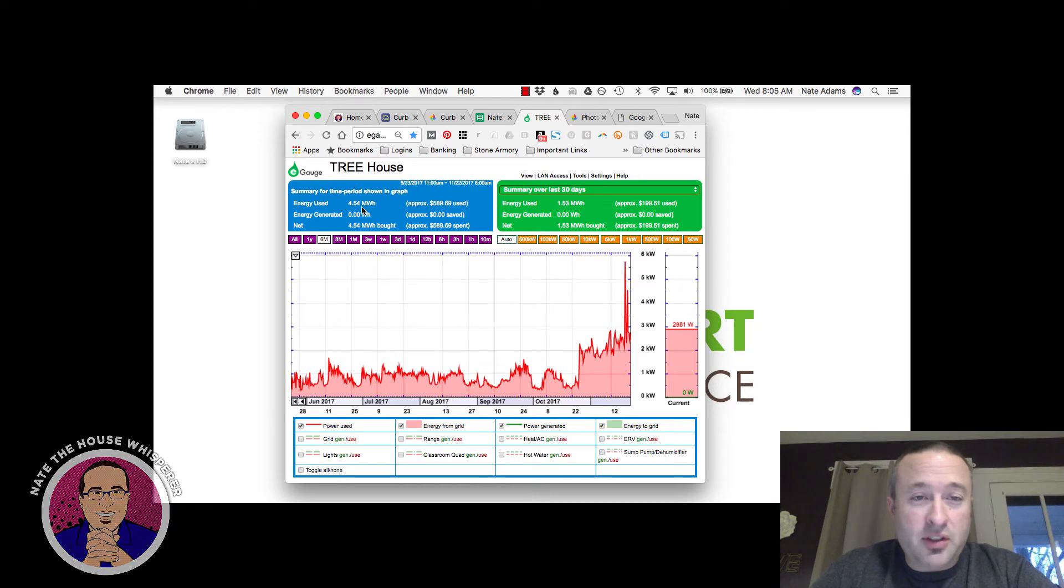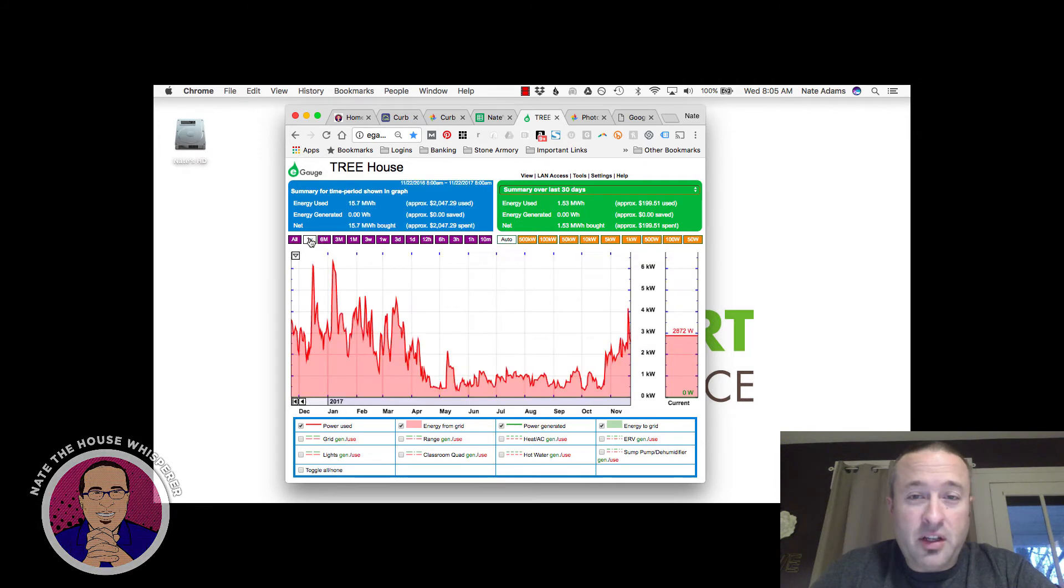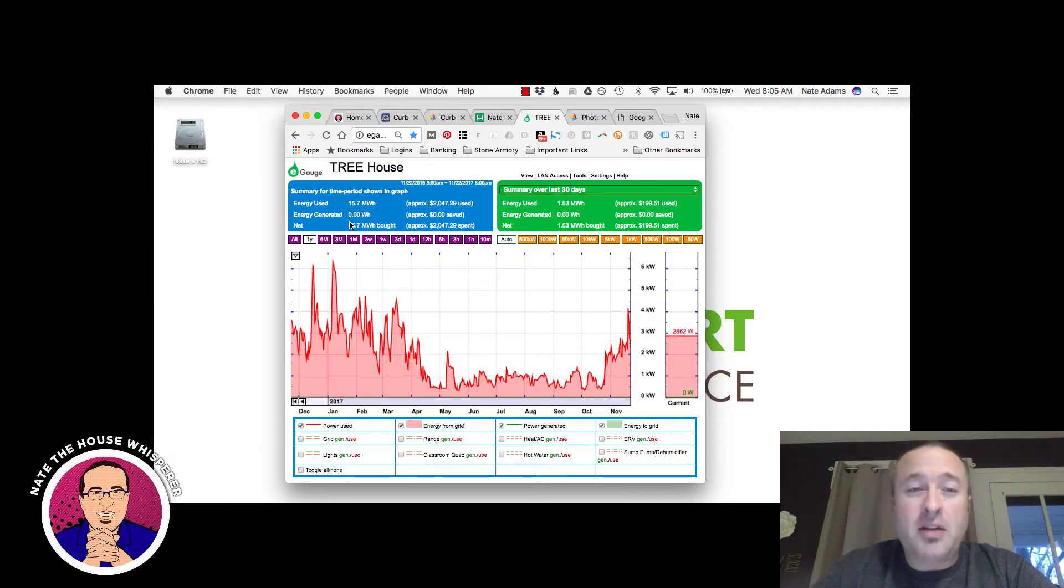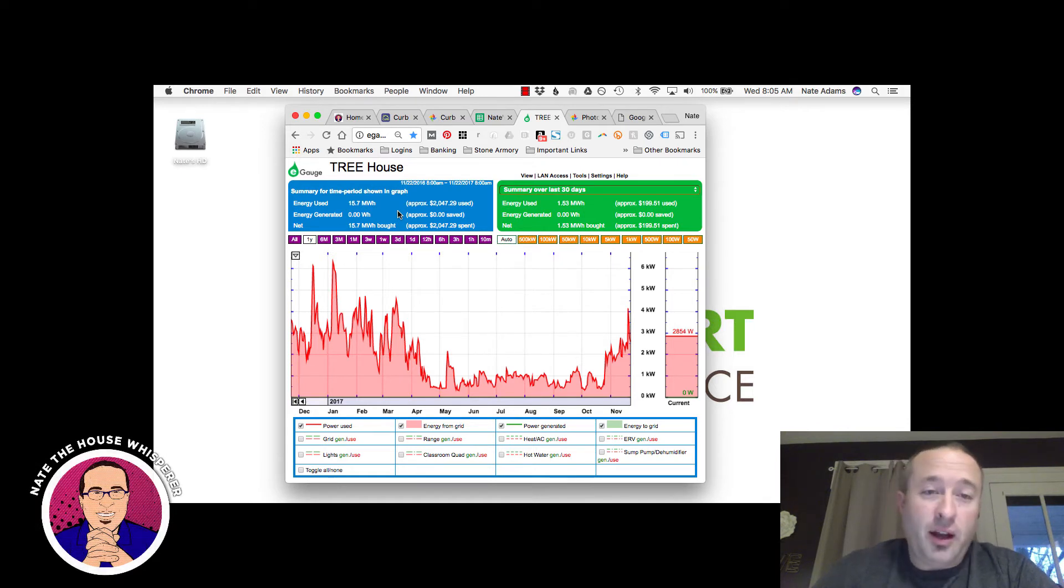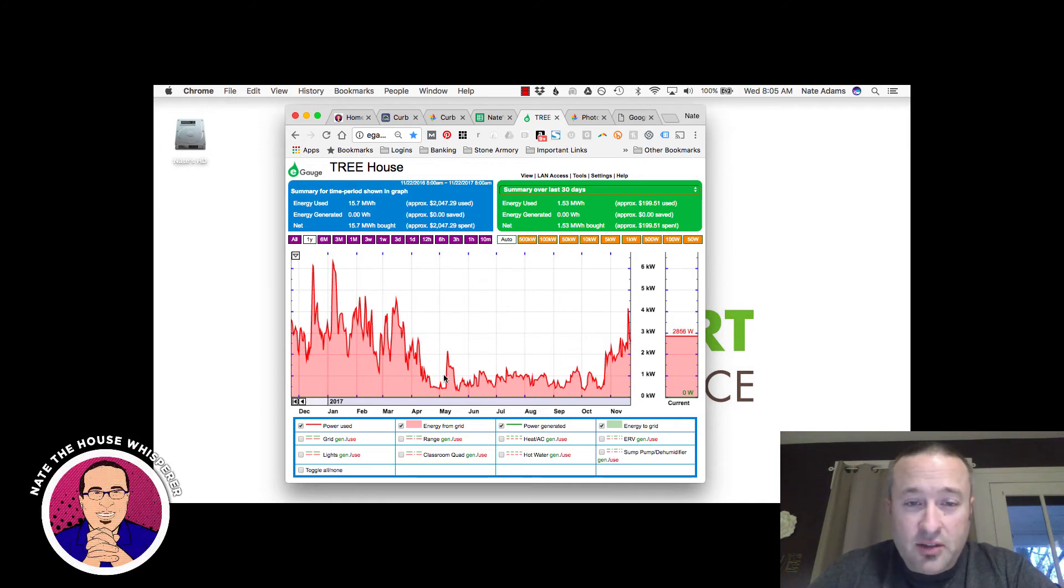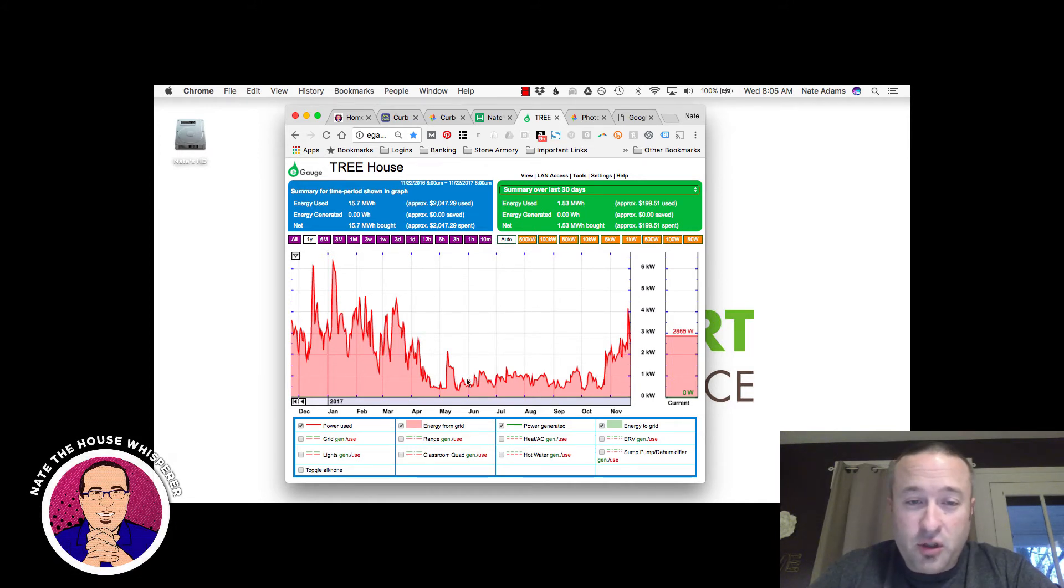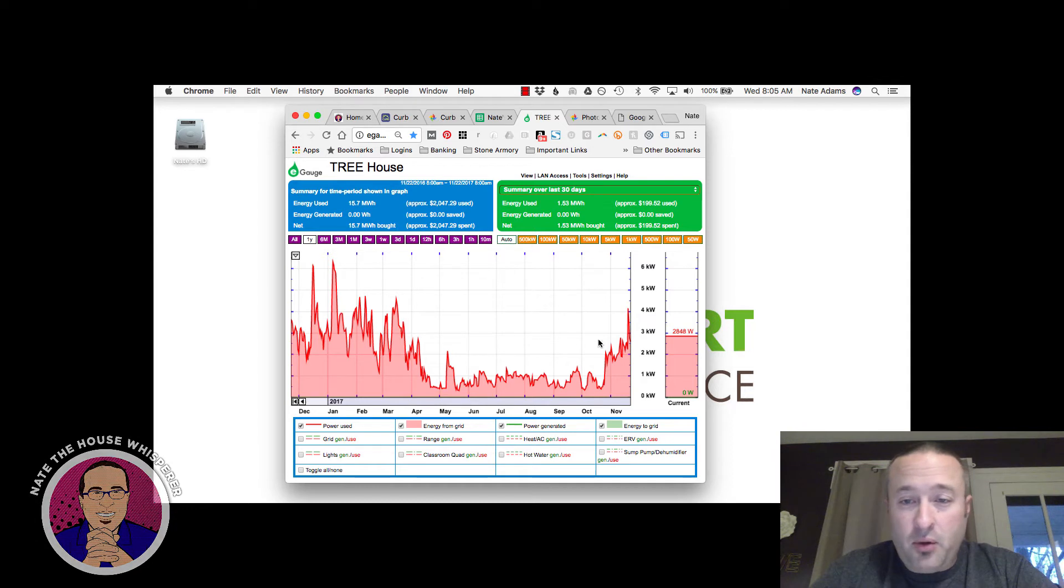So, but it is nice that you can see what's going on. You can select whatever time period you want going back. So in the last six months, it's used, what is that, 4500 kilowatt hours. And if we go back an entire year, it's used 10,700 kilowatt hours. And this matches up to the utility data I've been able to get for the college. So it's close enough that I trust it.